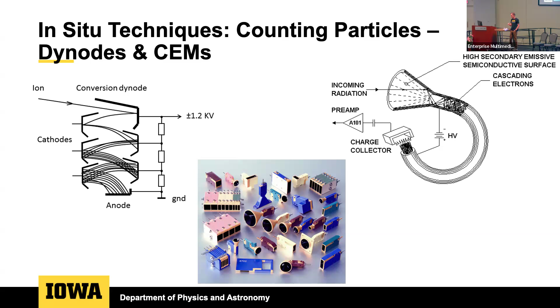This case here is set up as individual conversion dynodes, individual surfaces that create secondary electrons, but you can also just have a continuous surface. So this is a CEM, channel electron multiplier, and the trumpet up here at the top is where the incoming particle comes in, and then it creates a cascade of electrons, and by the time you get out the bottom, you've got 1,000,000 electrons that you can put into your electronics, measure as a charge pulse, and create a digital signal. So CEMs are commonly used in spaceflight instruments as detectors.